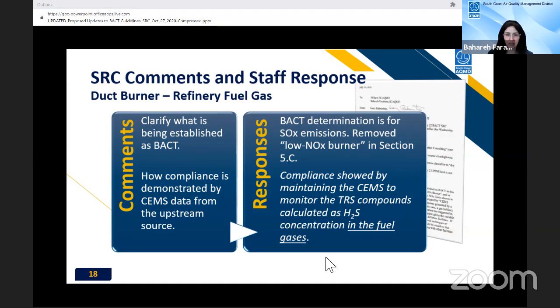Okay, so about the name—see what happens if you look at a CEMS system, like, for example, what David was referring to with fuel meters. When we say CEMS, that's continuous emission monitoring systems for NOx and SO2. This is a part of the CEMS—the TRS monitor, which is a GC-SCD, and also the fuel meter, which is required to measure mass emissions in pounds per hour, is a component, a part of the overall CEMS/SEMS.